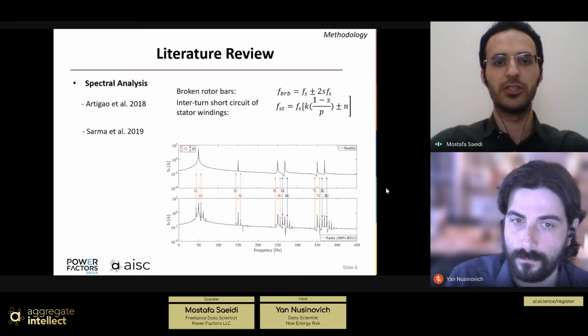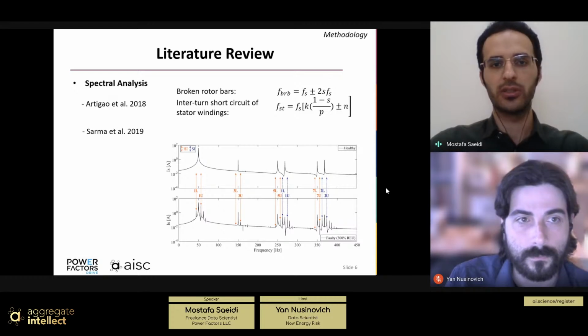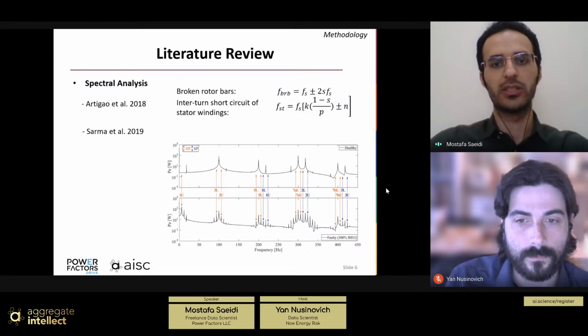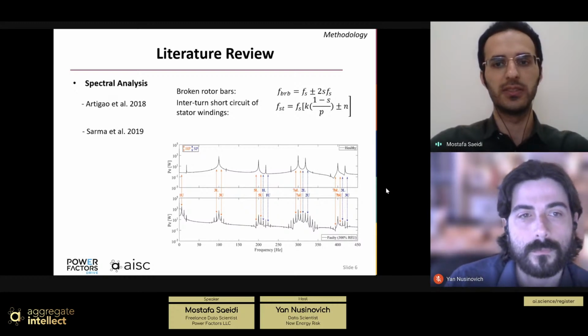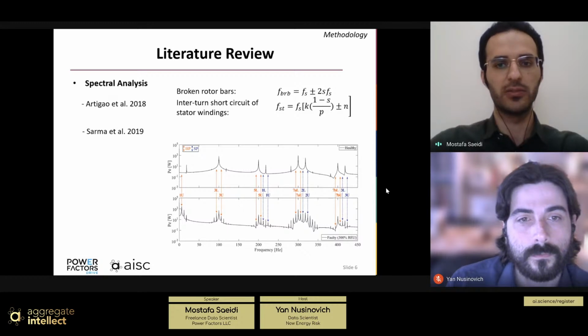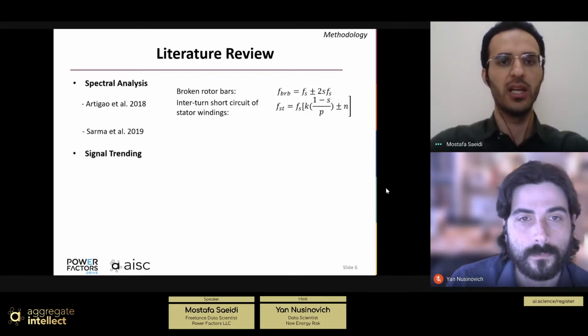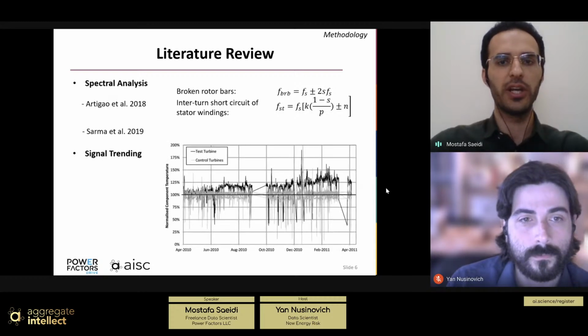The other paper suggested that not only can we focus on the stator current frequency spectrum, we can also extract the frequency spectrum of active power, generated active power, and it's the same thing. When there's a fault, there would be some spikes in the frequency spectrum. The other method is signal trending, and the whole idea of this method is comparing the operation of one turbine with other turbines or the average of other turbines.